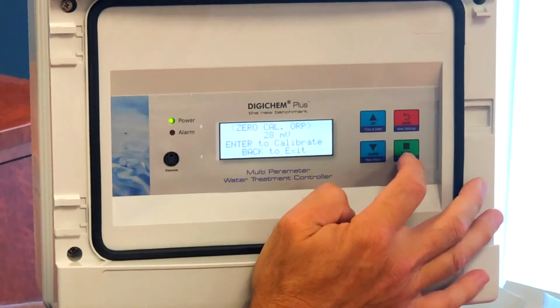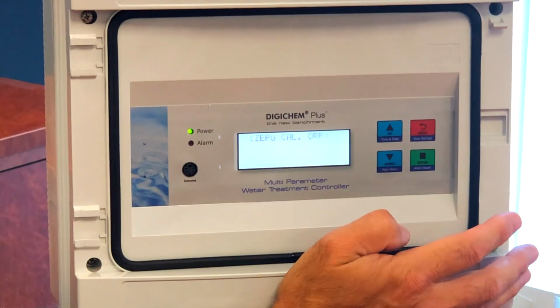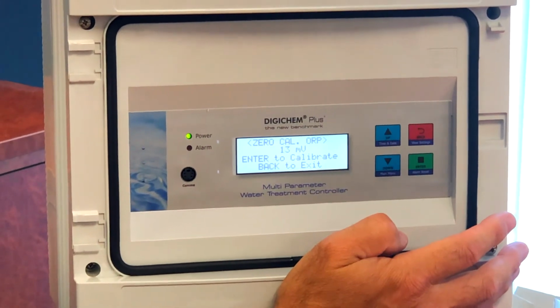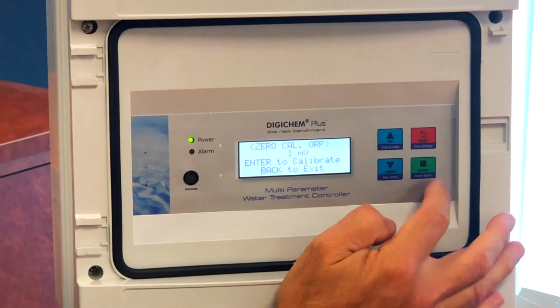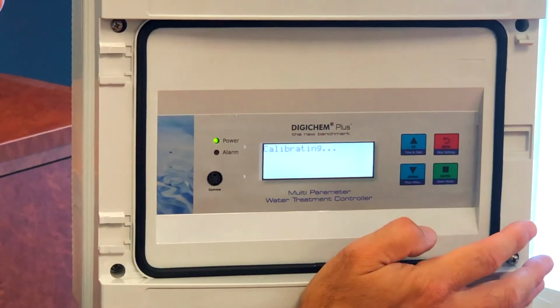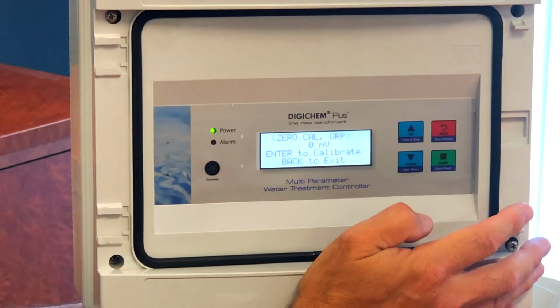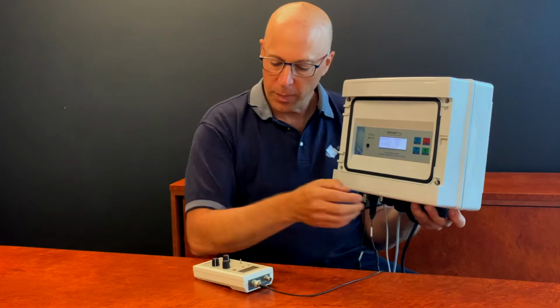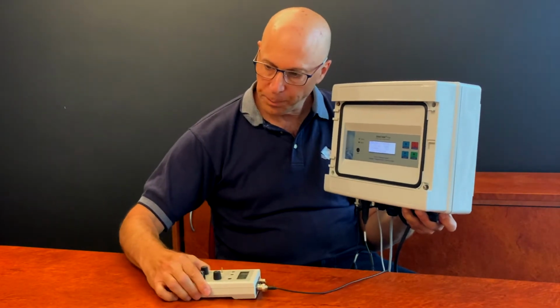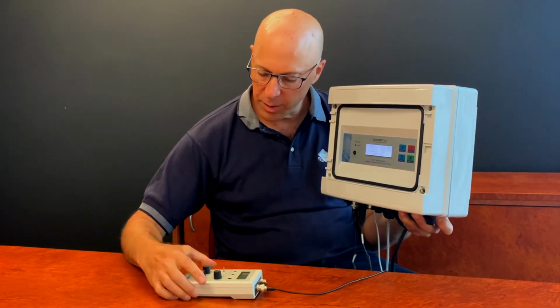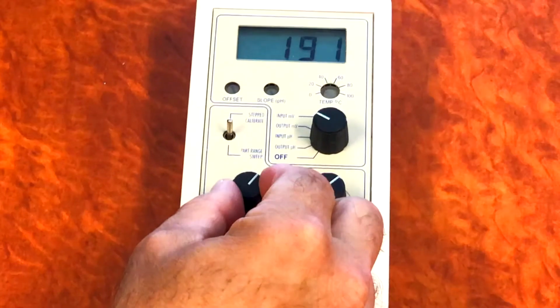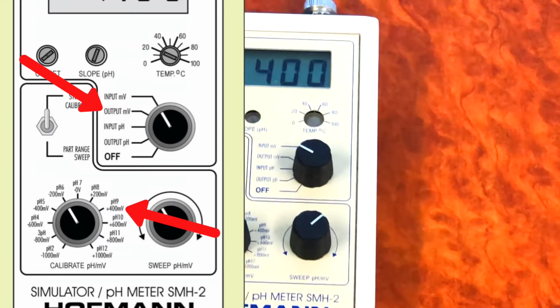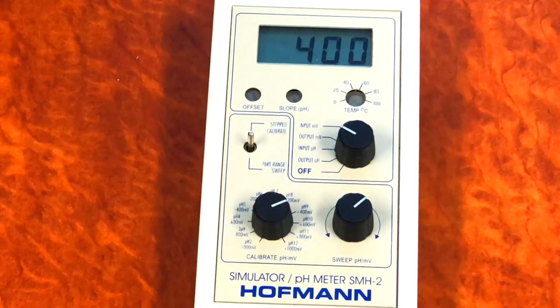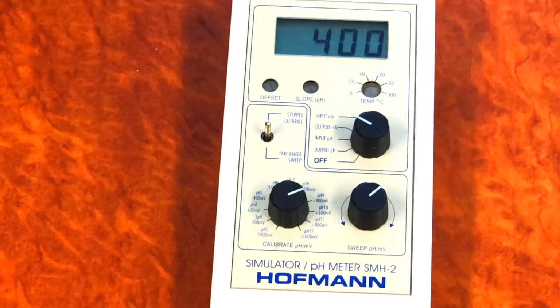When you press enter, it will calibrate the value to 0. If it keeps on displaying a number, you can continually press the enter button until you're satisfied that the reading stays at 0. Step 2 is to change the setting on the simulator. In other words, we change it so that it outputs a value of typically about 400, which is a typical reading that you find in cooling tower applications. So you can see the simulator is now outputting 400 millivolts.